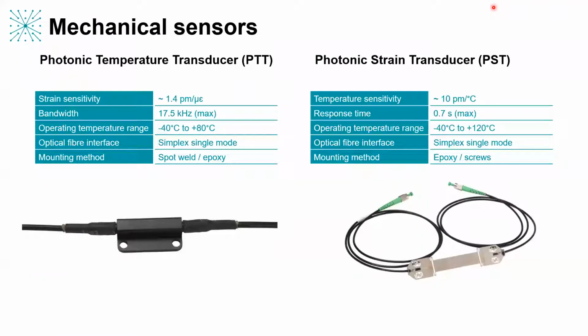And then just to give you an idea of what our mechanical sensors look like, we have the temperature sensors on the left and the strain sensors on the right. Those can be attached in any number of ways, like spot welding, epoxying, and even screwing them onto surfaces. That allows us to pick up the temperature of that surface, or the strain of it and the vibration. Now, one point I want to make, which is important, is the strain measurement. We can measure what's known as absolute strain, which means that we don't just see the change in strain. We can monitor very slowly changing expansion and contraction of materials, which is really interesting for example, for overhead line sag, because at any point in time we can tell you exactly the expansion of that line due to heat or any other issue, which is very difficult to do with most other technologies.